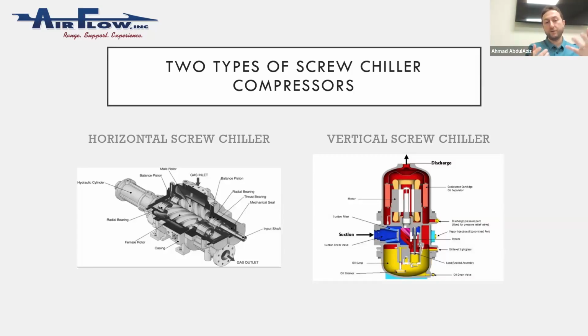If you compare standard horizontal screws to vertical screws, you'll find somewhat less noise from the vertical compressor compared to the horizontal one. Apart from this, both are in use. I'm not sure if all manufacturers have vertical designs—I think only limited manufacturers develop their own vertical screw, but all manufacturers use horizontal screws.